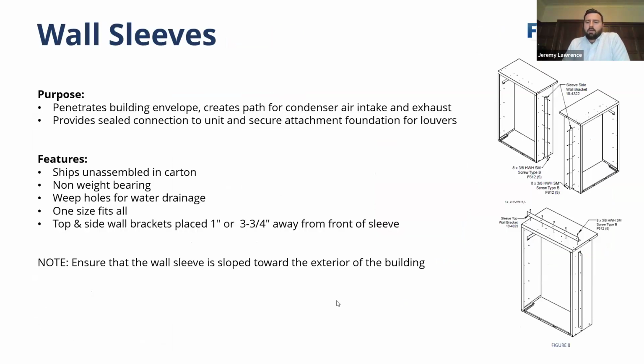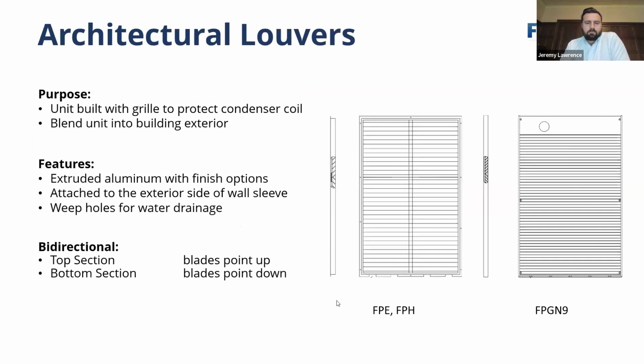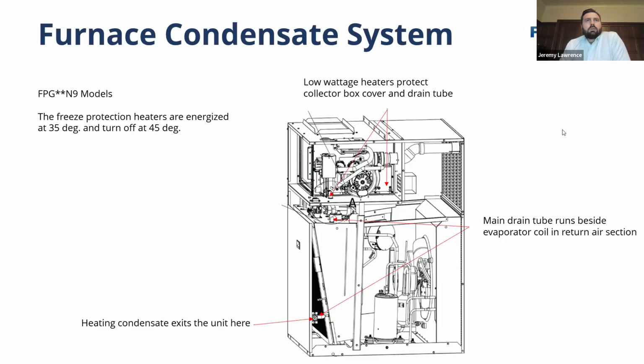Wall sleeves, again, must be on an exterior wall because these systems are a little more, well, lower. Their sleeves don't carry the weight of the unit quite as much. Same architectural louvers. If we're dealing with the high efficiency gas, the gas vent is incorporated into part of the louver. In the high efficiency gas system, they did consider the potential for freezing condensate, especially when these systems are running in the winter. So there are small heaters built into these units to ensure that the condensate flows correctly and no issues come about.